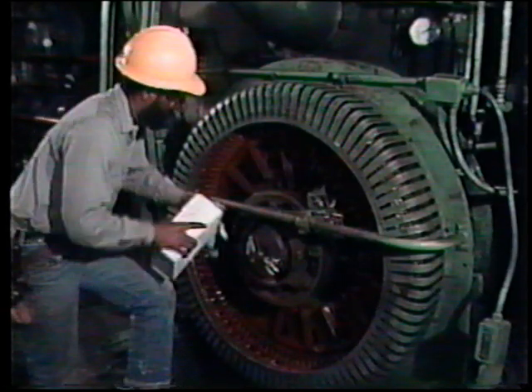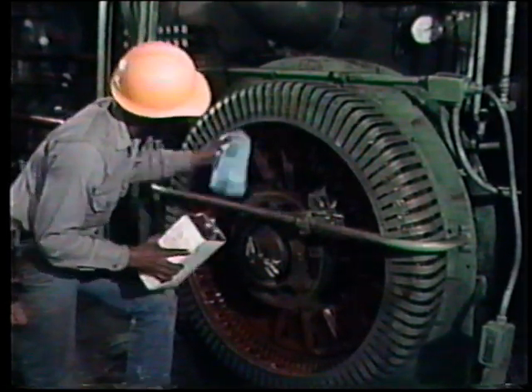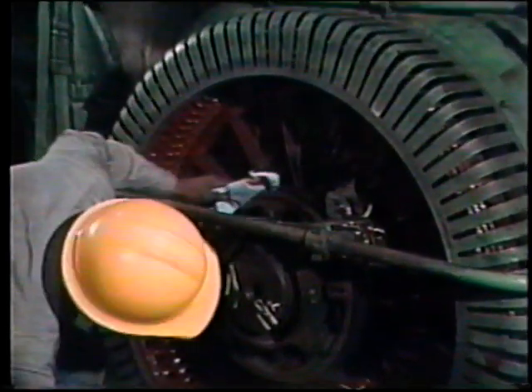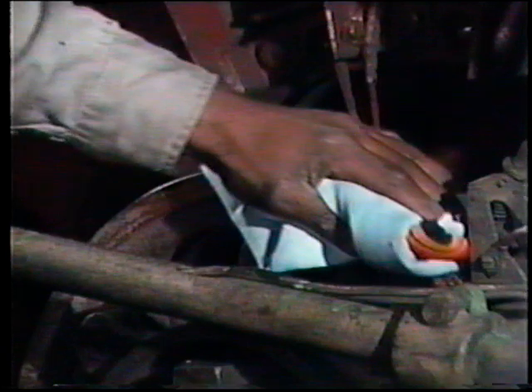The slip rings also should be carefully inspected. Check for grooving, discoloration, and contamination. Dirt and other contamination could cause a poor conducting path. Here we have some minor discoloration, and so we use an approved solvent and a non-abrasive wiper to clean them. If you find grooving or any other serious problem, report it to your supervisor.